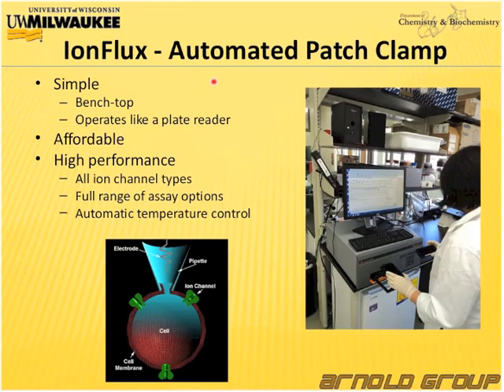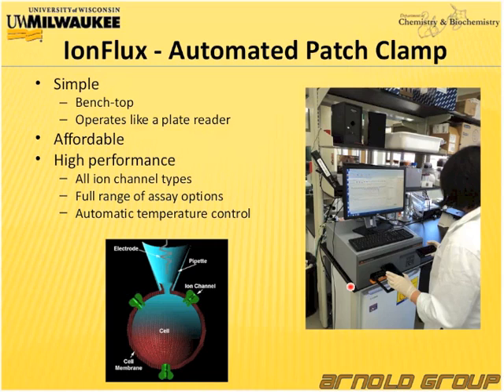For that purpose, we purchased the IonFlux, which is an automated patch clamp instrument, depicted in the picture here. It is a benchtop instrument that operates like a plate reader. Indeed, we are using multiple plates to carry out this assay. The instrument was affordable and gives us very high-performance data. I want to mention that this instrument is not only capable of assaying the GABA-A receptor, but all ion channels in general.